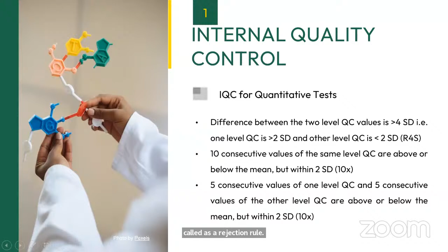If 10 consecutive values, mixed and matched across both levels or from the same level, fall on one side, it will be considered a rejection rule. The last rule here: 5 consecutive values for one level of QC and 5 consecutive values for the other level, if they fall above or below the mean but within 2SD, it is again a rejection rule. So if there are two levels, then 5 plus 5, the total number of values should be 10 or above. If they fall only on one side, even if within 2SD, it will be called a rejection rule. So these are the basic IQC rules which you have to follow if you are running one level of QC or two levels of QC.